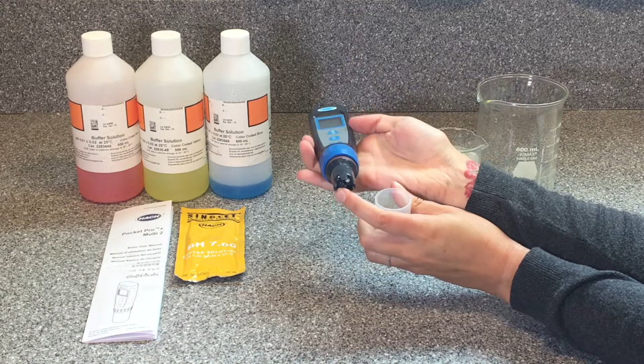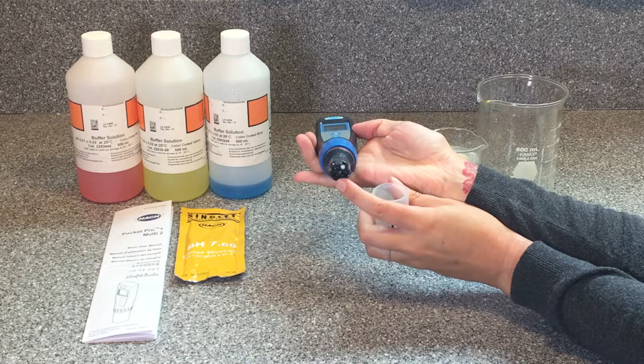The first thing to know is that the Pocket Pro should always be stored with a cap full of water. This is to prevent the sensor tip here from drying out. If the sensor tip dries out, it won't work and will need to be replaced. So always make sure that you fill it with a cap full of water.